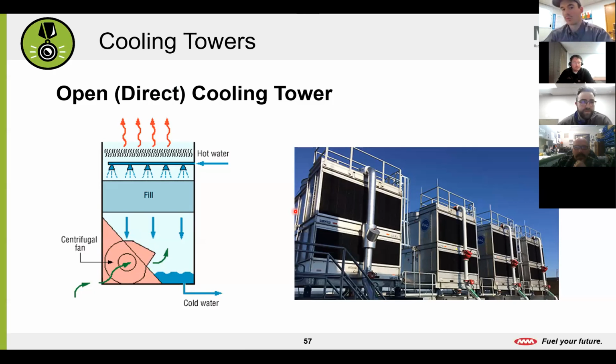Okay, so now we'll just move on and talk about cooling towers. When we're talking about those water-cooled chillers, and I kept saying it would go to the cooling tower where we would reject heat, that's what we're talking about now. There are going to be two types of cooling towers we'll talk about. One is an open style cooling tower, and one is a closed style cooling tower. The first one we'll talk about is your open style cooling tower.